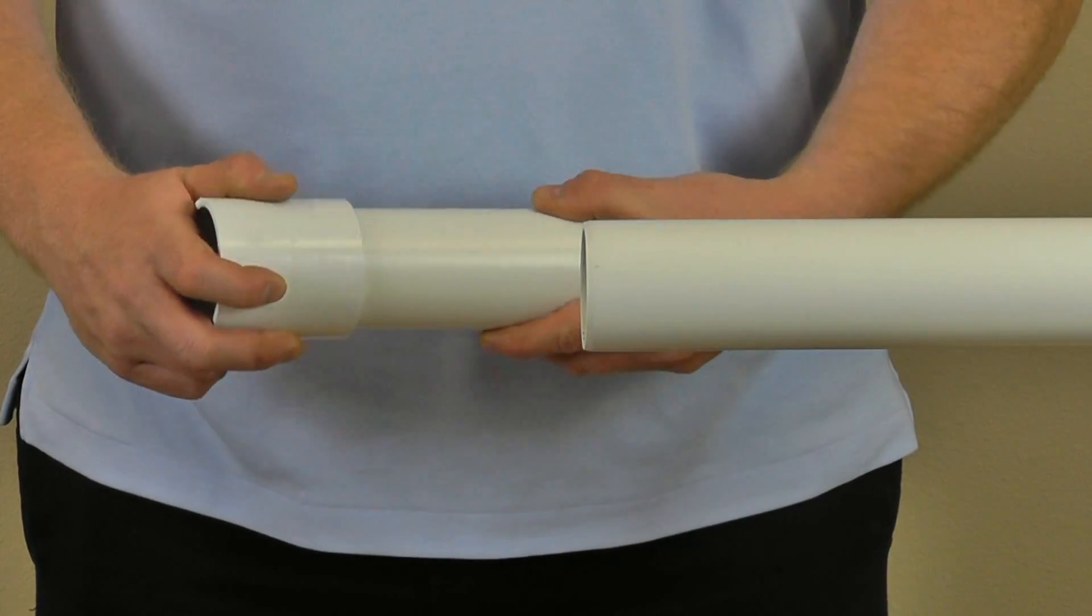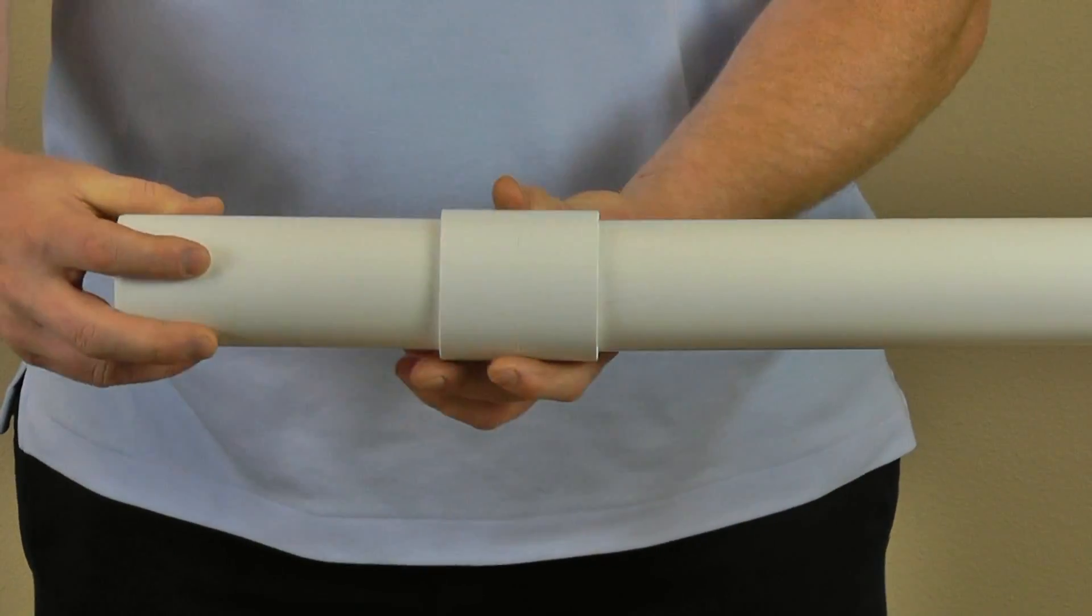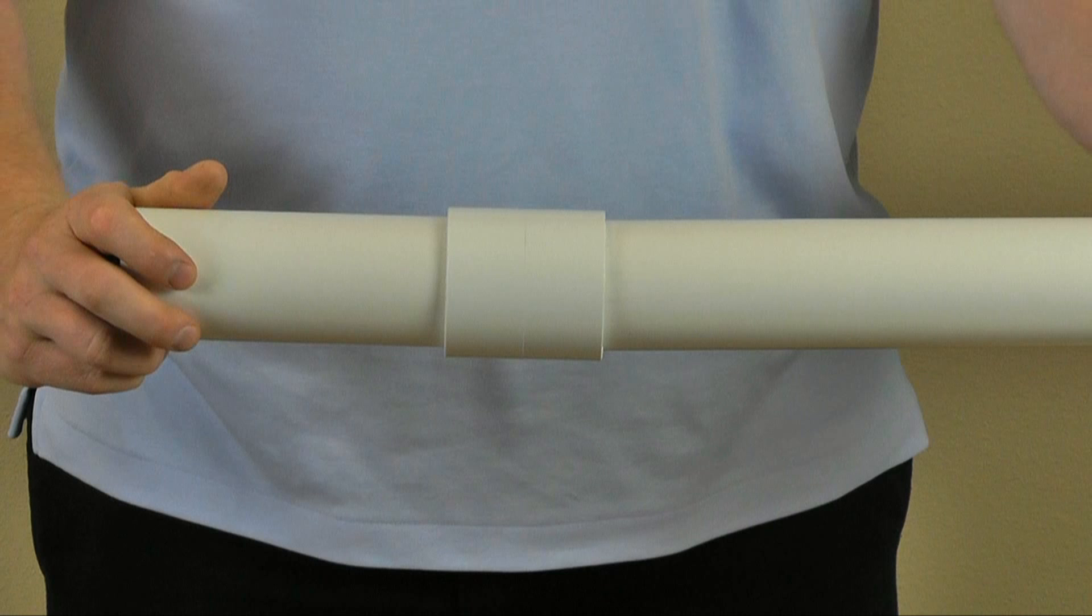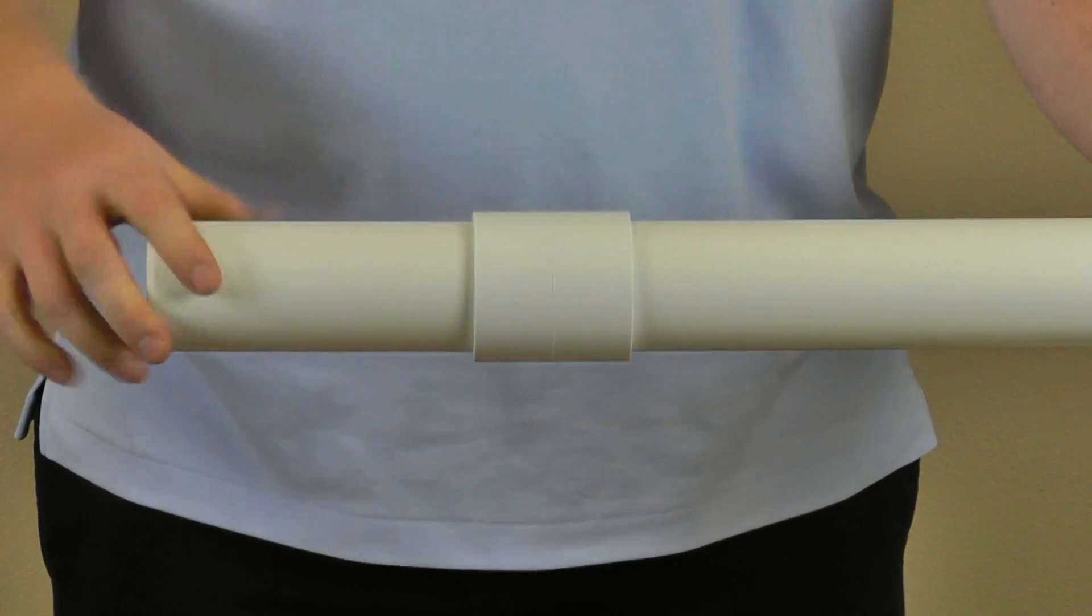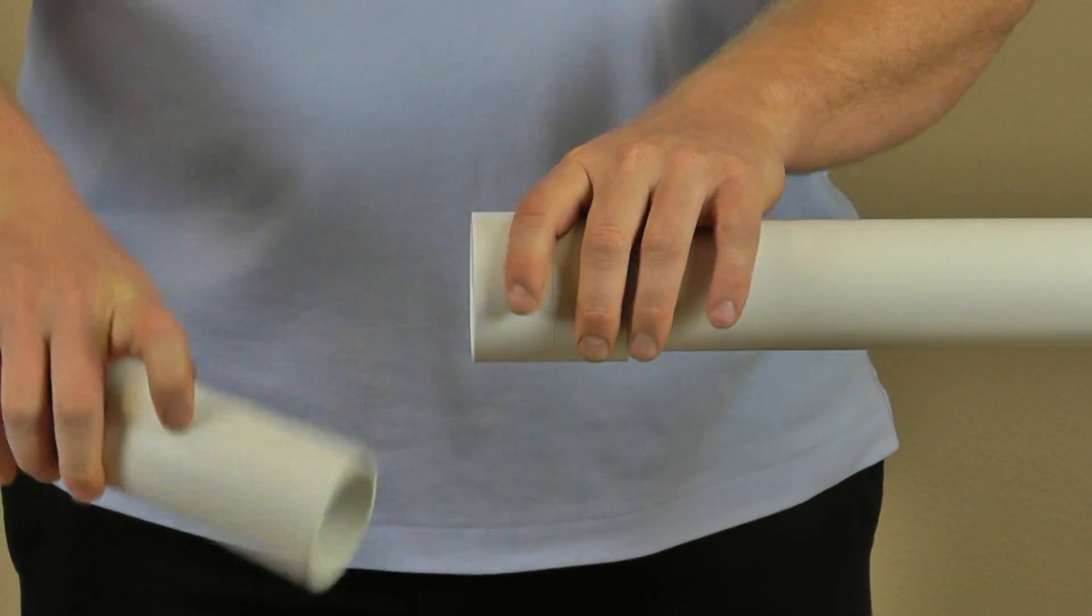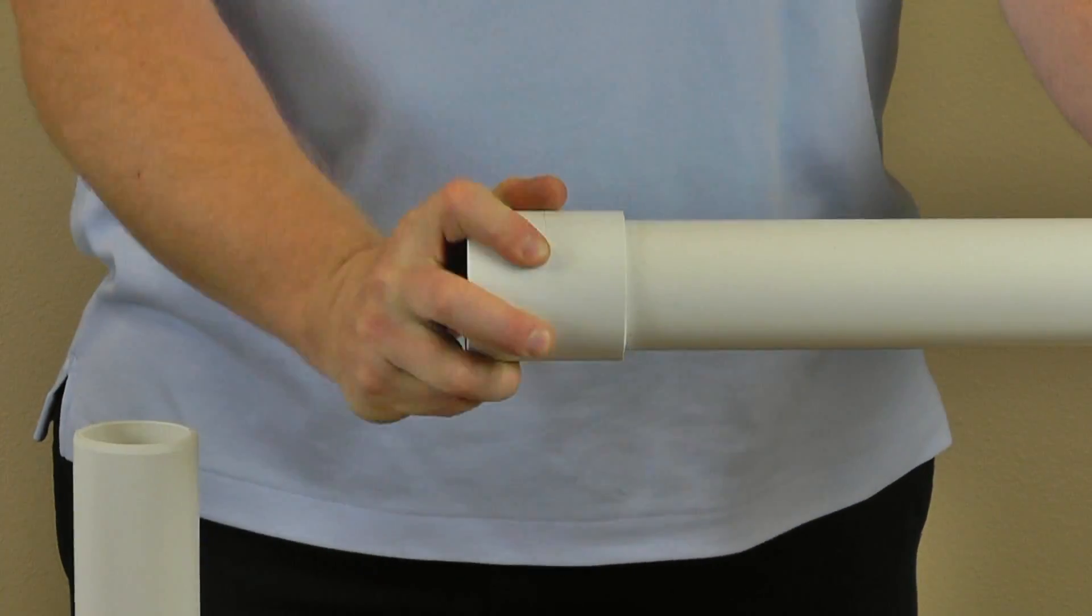Second, check the dry fit of each joint. A good dry fit is confirmed when the pipe enters the socket 1/3 to 2/3 of the socket depth before binding. This is referred to as an interference fit. If the dry pipe is able to be fully inserted into the socket without interference and is loose or wobbly, it should not be used.